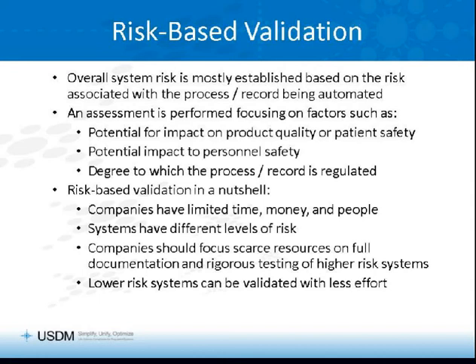You're going to generate typically more documentation, and that documentation is going to be thicker because you're doing more specification work and testing work. For the lower risk systems, you can get away with doing less, and the FDA actually expects that—they expect you to focus on the higher risk systems. So in a nutshell, risk-based validation means that lower risk systems can be validated with less effort. The caveat is that because you're doing less, you may miss some things you wouldn't have missed if you'd done more. But since they're low-risk systems, the impact of the things you might miss is probably going to be low.